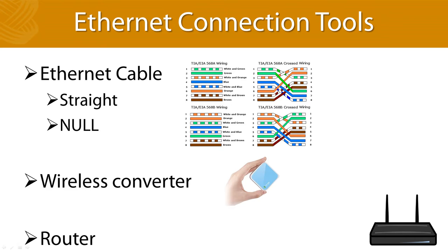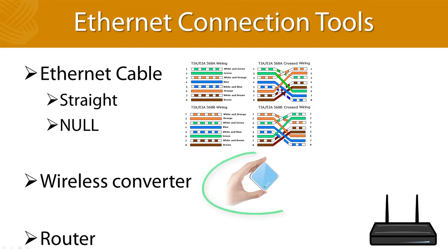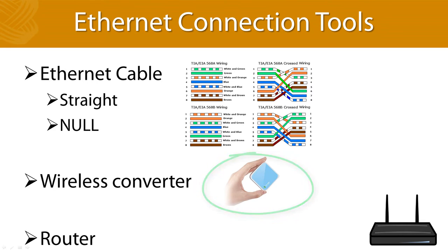However, most relay testing devices use straight through cables. You may not need a special cable even if a null is required because some laptops will auto-switch to the configuration required by the system. This can make troubleshooting difficult as everything will be fine with an auto-switching laptop and then somebody else comes with a regular laptop with the same cable and it won't be able to communicate. I carry a 25-foot ethernet cable with me for direct communication or I would use the little portable router shown between the fingers on the screen that was another cheap Amazon purchase for $22 that allows me to connect to devices wirelessly. Or you might consider bringing a wireless router with you so you can connect to all of the devices at one time which will allow you to communicate to more than one device simultaneously, something you can't do with a serial connection.